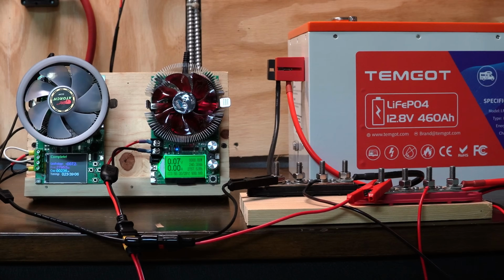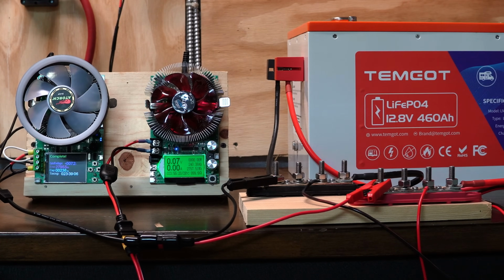So my conclusion from this test is that this Temgot 460 amp hour battery definitely does live up to its rated capacity. And if I could discharge this at a quicker rate, I have no doubt that we would easily attain that 5,888 watt hours.